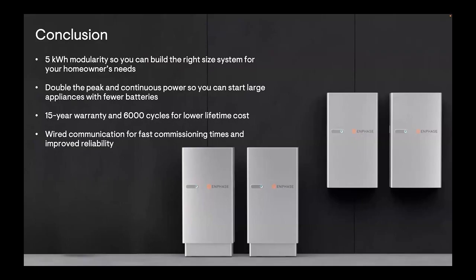So in a nutshell, these are the key benefits of the 5P: 5 kilowatt-hour modularity, which allows you to build the right size system for the homeowner's needs, so you're not overselling them on storage capacity. It has double the peak and continuous power of the previous generations, making the system much more capable of starting large appliances like air conditioners. There's a significant improvement to the warranty—15 years instead of 10, and 6,000 cycles instead of 4,000. And wired communication allows for much faster commissioning times and improved overall reliability of the system.